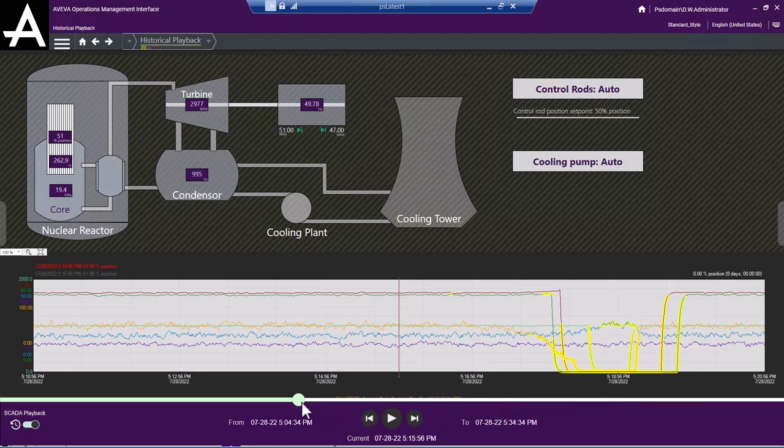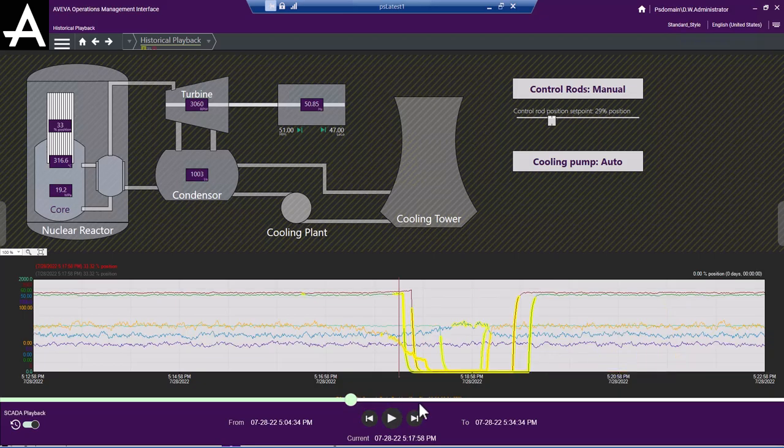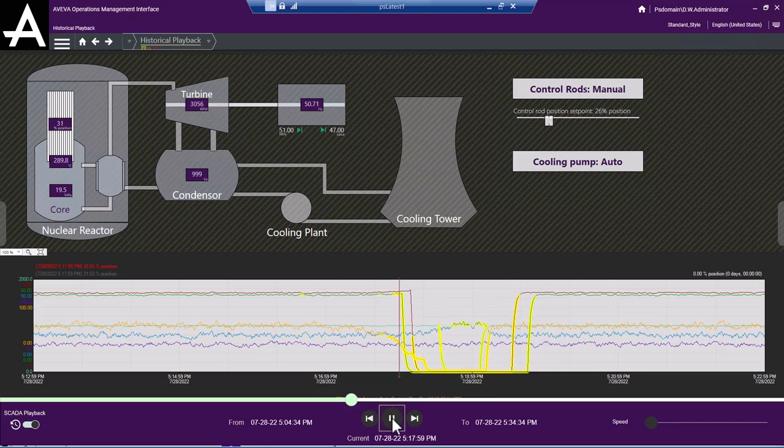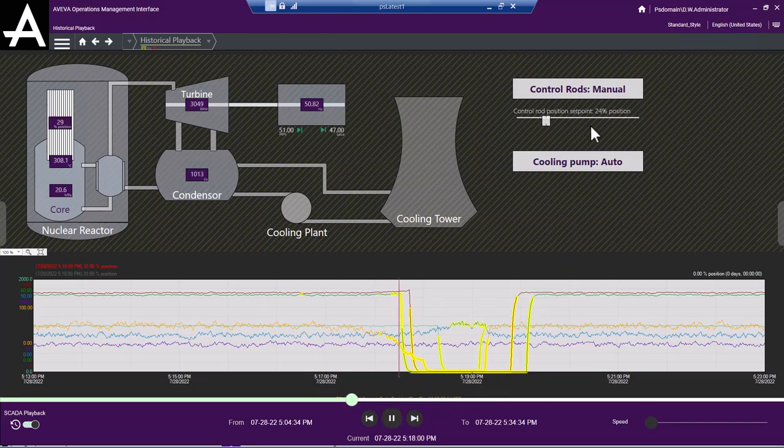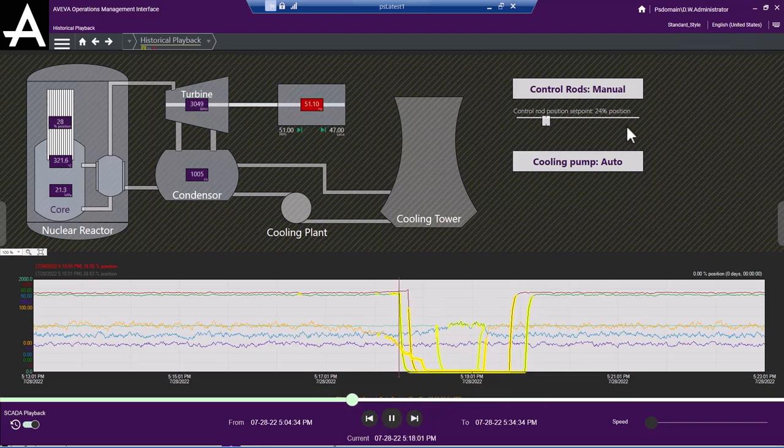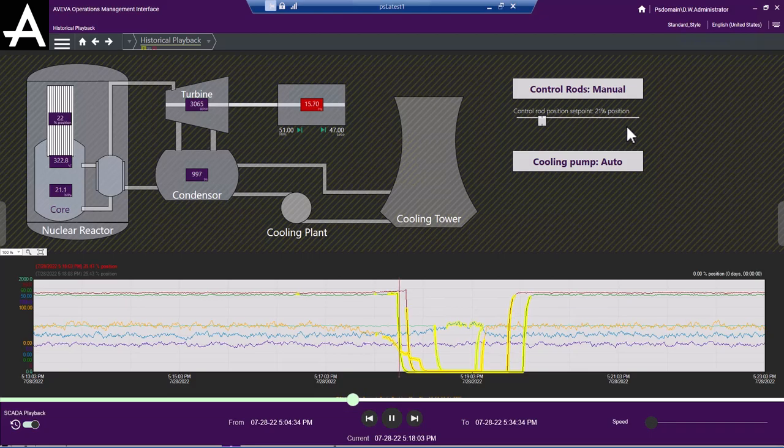Things like tag name, description, engineering units, alarm limits, and the like had to be historized, or they would not show up during playback. For the 2023 release, we improved that. We automatically detect if there is no history available for specific attributes. We'll switch back and show the live values on the screen.